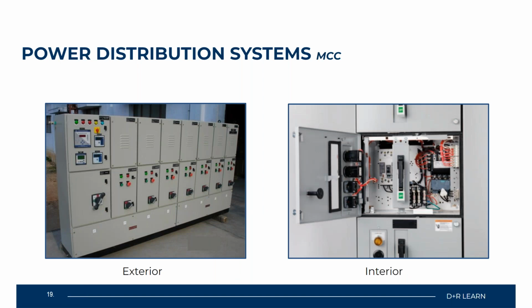Next, we have the MCC, part of the power distribution system, or your motor control center. The MCC is an assembly that is placed inside of mechanical rooms to control some or maybe all of the electrical motors in a certain isolated or central location. It consists of multiple enclosed sections which have a common power bus, with each of the sections containing a combination starter. So you'll have your motor starter, your fuses, your circuit breaker, and your power disconnect associated with the MCC power distribution system.